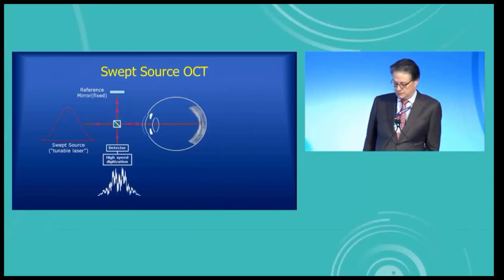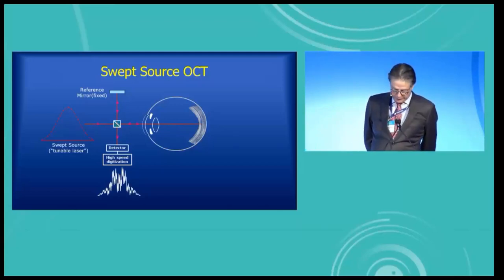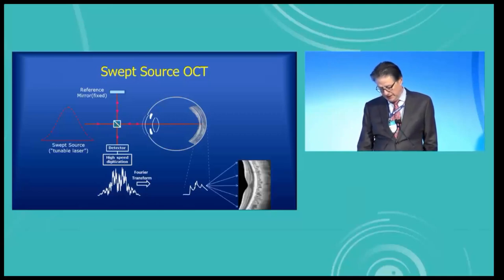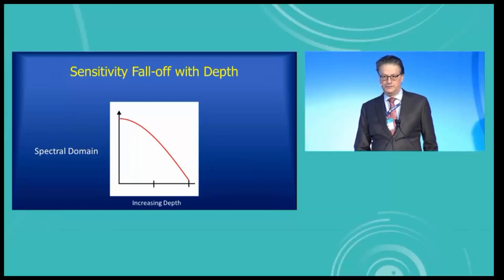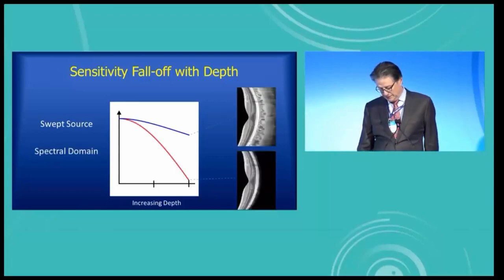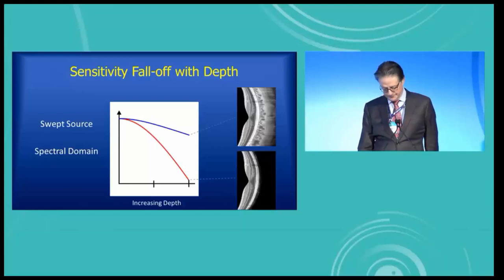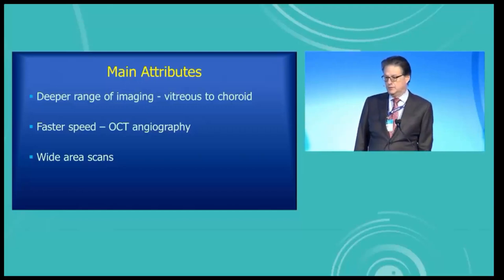Swept source OCT goes through the spectrum of wavelengths sequentially in order, and it builds up an interferogram over time. Just like spectral domain OCT, that interferogram is decoded by a Fourier transform to get an A-scan, and many A-scans make a B-scan. What's different is that the sensitivity falloff is much different than spectral domain. Swept source gives you an image all through the depth of the eye — from the vitreous, retina, and choroid — all pretty much simultaneously. The main attributes of swept source OCT are deeper range of imaging, higher speed — which is really an attribute for OCT angiography — and it also lets us do wide area scans or big volumes.